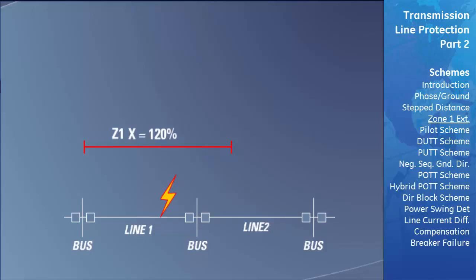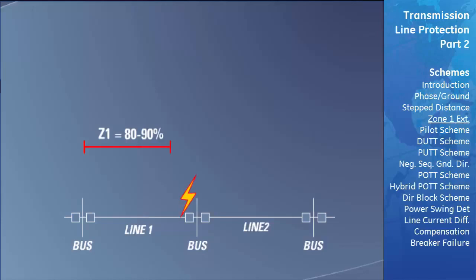Once the breaker is opened and the fault cleared, the relay automatically re-closes the breaker and re-energizes the line. After re-closing, the relay uses the standard Zone 1 characteristic and underreaches to protect only its own transmission line. If the fault was permanent and located within the newly shortened Zone 1, the relay will trip again to clear it. If the fault was transient, the first trip removes the fault and power transmission resumes. If the permanent fault reappears outside the shortened Zone 1, Zone 2 protection will clear it after its time delay, or the adjacent line's relay will clear it in its own Zone 1.